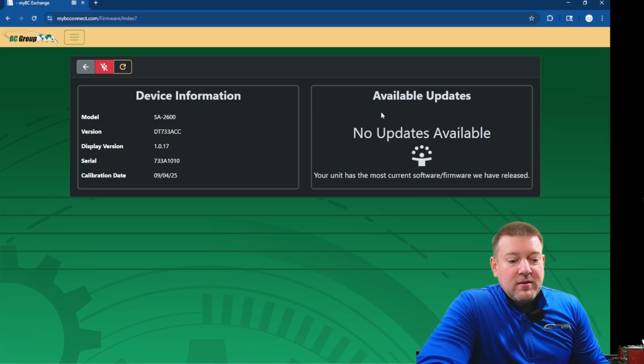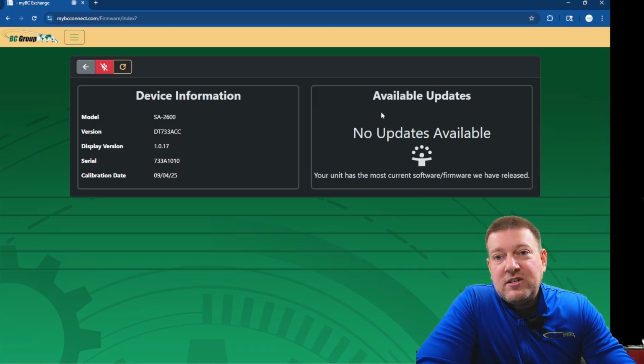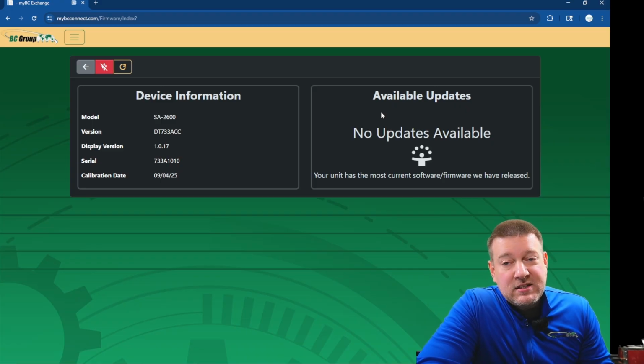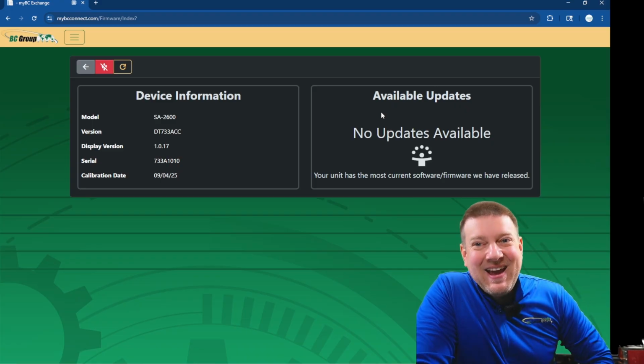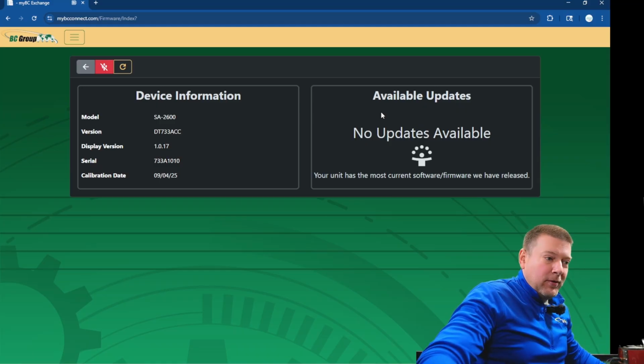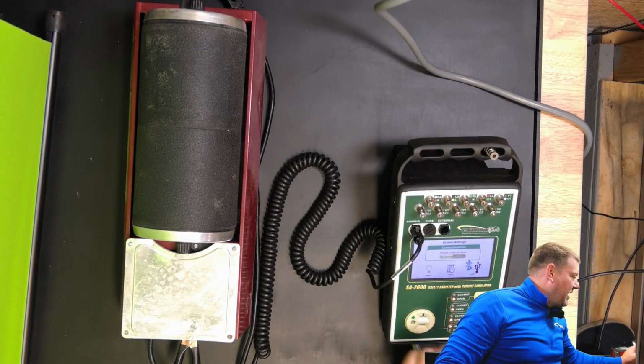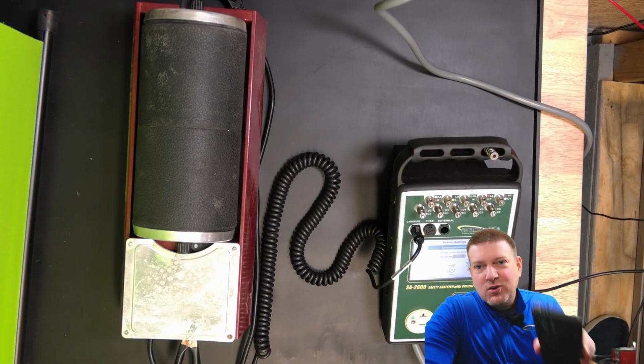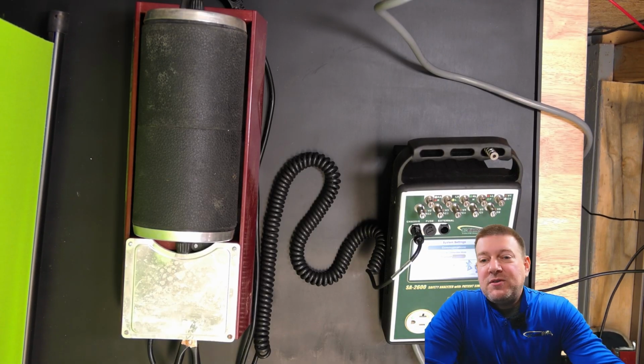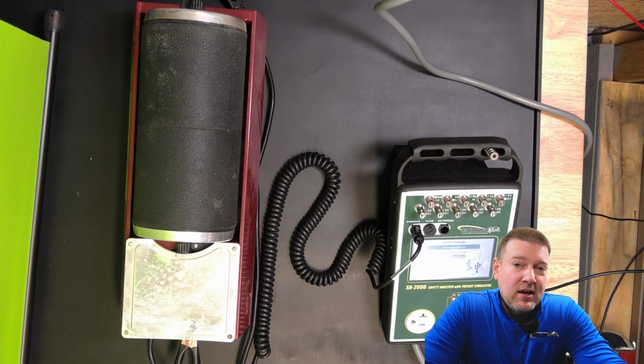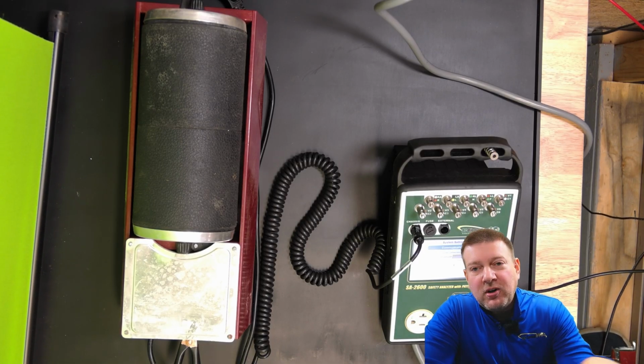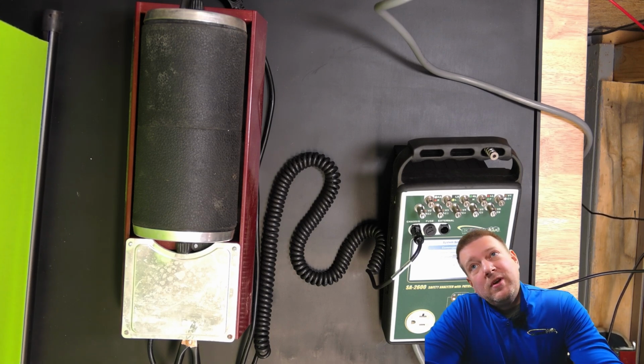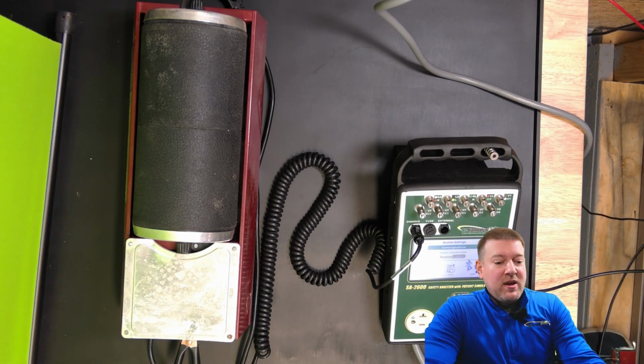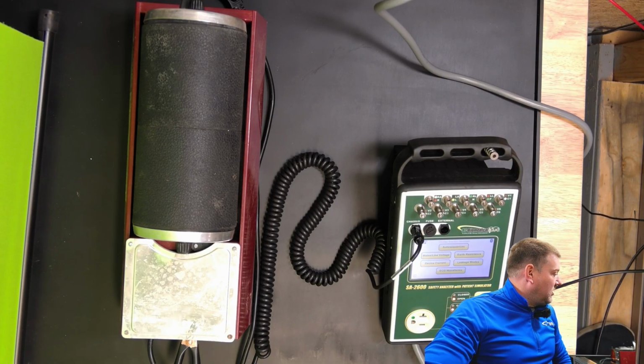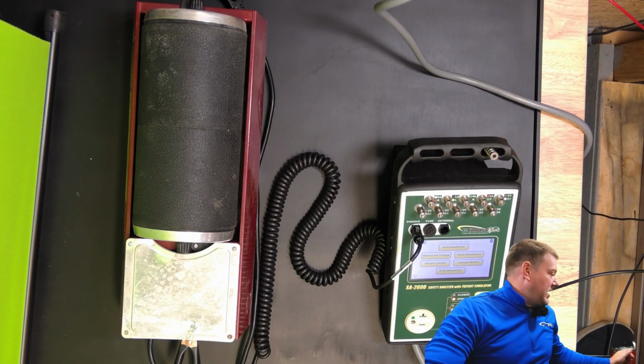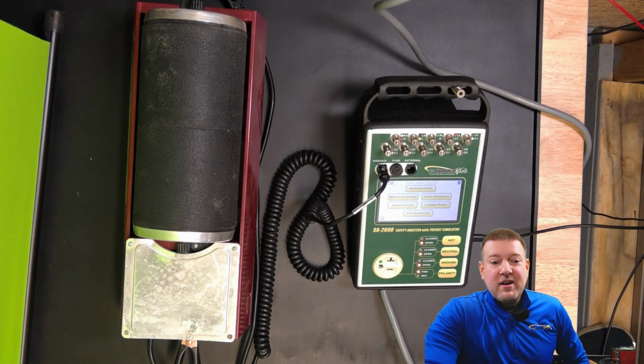Okay, guys. So our electrical safety meter, we checked it. We made sure the leads are good. Its calibration date is good. There's no firmware updates. It's safe to use. All right. At least for today, it is safe to use. So let's hop back over, and I'm going to set this guy back on Bluetooth. This is going to be very important because we are going to use Bluetooth to control the device, which allows us to do automated tests, and it allows us to save those tests here on your smart device so that you can export those results and attach them to work orders, etc. Okay. So I have my device back. We're going to click it on the main screen, and we are ready to do some tests.